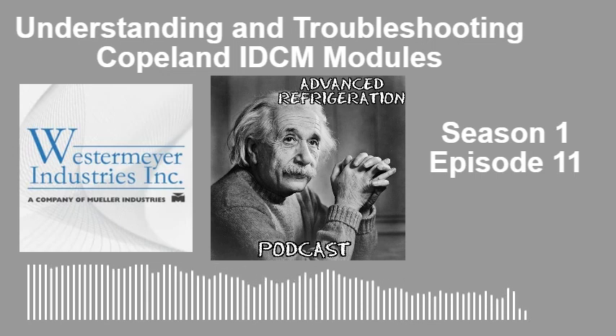One of the things I did want to add when you were talking about the demand, making sure that you're, typically you always want your time delays to be set to make sure that it doesn't short cycle the compressor upon an abrupt turn off and turn back on. One of the things I can disagree with is with the IDCM module. A lot of times, you start off your compressors, from number 1 over, you start 30 seconds, a minute, a minute 30, 2 minutes, and so on and so forth, however many compressors on your suction group. On anything with an IDCM, just put it to 0. Don't screw around, because what will happen is if the controller has its signal and the RO is calling for that particular compressor to be on, and it doesn't sense that amperage within a certain amount of time, it's just going to flake out and fault out, and then you're going to be required to pull the control power off of the IDCM module to get it back up and running.